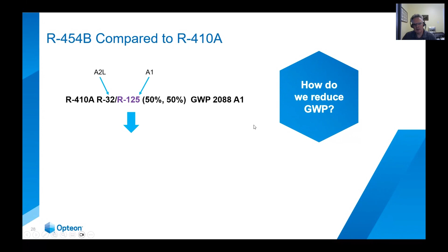But now the regulation came out and said, okay, we need a lower GWP. What are you guys at Chemours going to do? So, of course, we looked at it and thought, what can we do? We would like to come up with something that looks like 410A, but has lower GWP. So what we did is we said, okay, let's take 1234YF, which is used in the automotive sector and has a very low GWP. So we replaced the 125 with 1234YF, but both are A2L, so the blend ends up being an A2L. But look at the impact on the GWP. It goes from 2088 to 466, well below the 700 requirement that's in place in the US for 2025 for air conditioning. So that's how it came about.